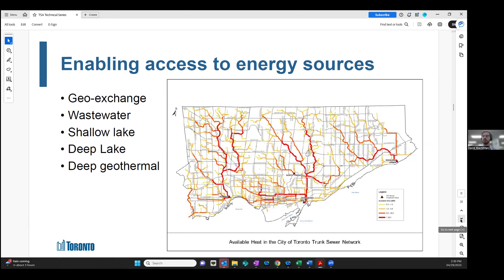So this is how we lead by example. I'll start on the far right, since we were just talking about wastewater. That project is currently under construction at Toronto Western Hospital — our first wastewater energy project. The project developer is Noventa Energy, and the client is University Health Network at Toronto Western Hospital. It doesn't look like that picture anymore; I need a more recent one. In the summer, the ribbon cutting will take place. It's already providing heating and cooling, currently being commissioned and working out the bugs before the ribbon is officially cut. The Mid-Toronto Interceptor, flowing underneath Dundas Street, is providing 90% reduction in emissions to the hospital — 90% less gas use at Toronto Western Hospital because of sewer heat. It's an amazing story: over 8,000 tons of CO2 per year entirely removed, all because the city provided access to both the sewer and the right of way, so Noventa could install their wet well and run pipes to serve the hospital. We have other projects now underway to try to scale that up.